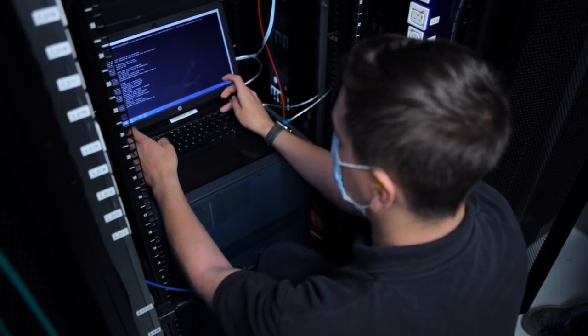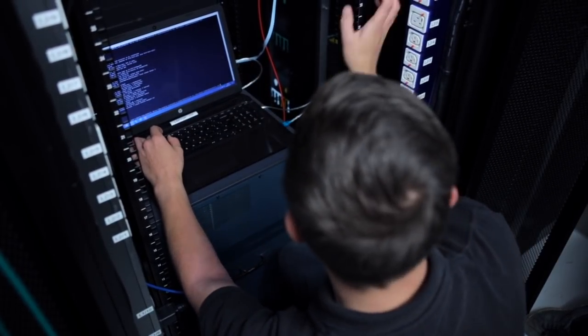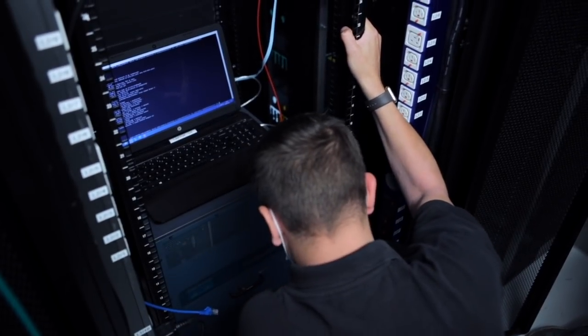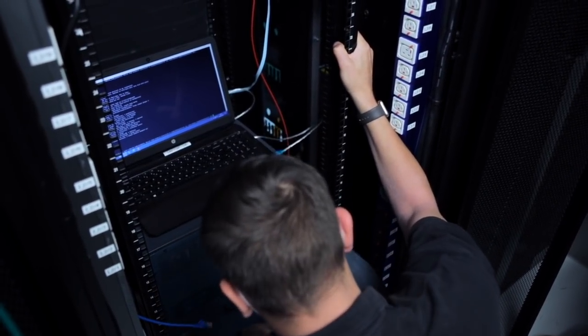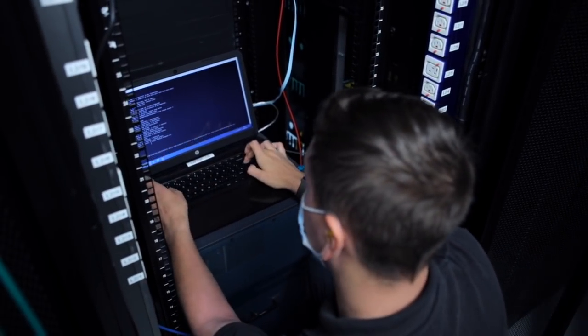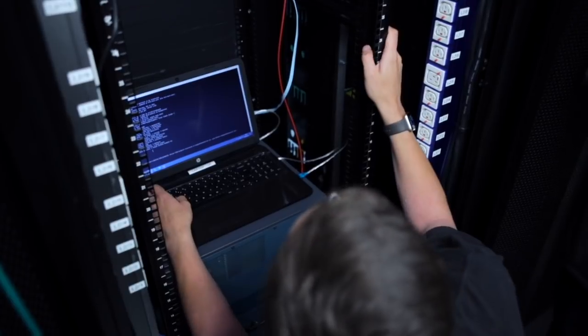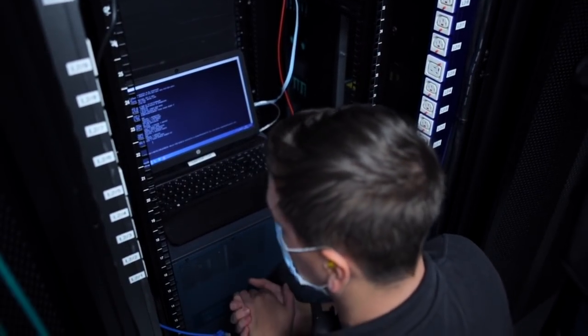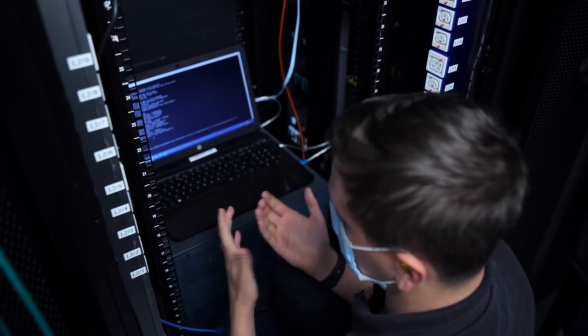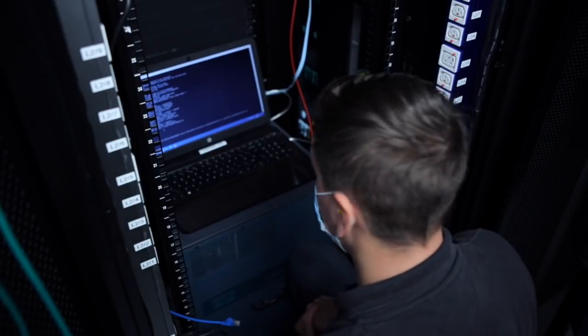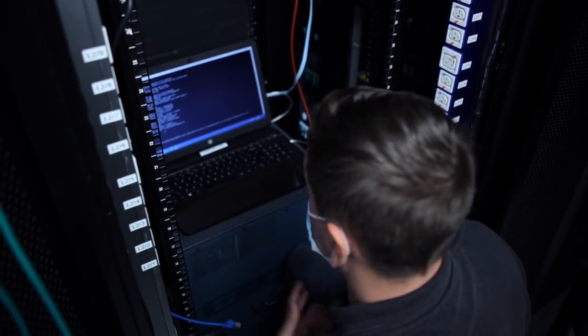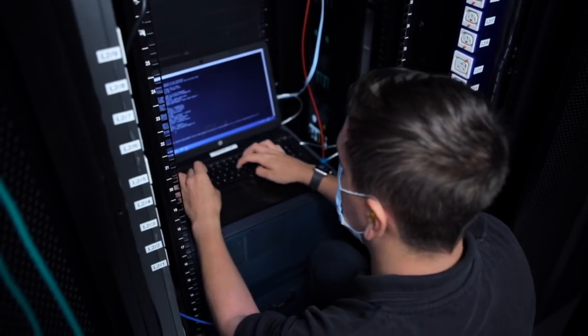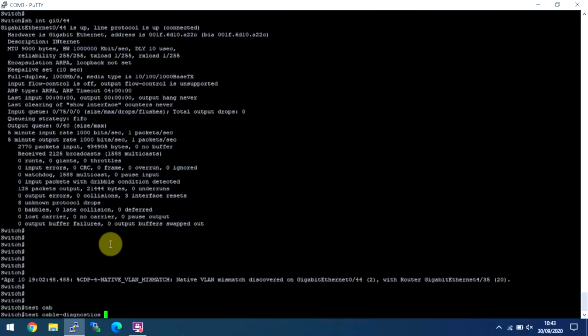What I'll show you now is the cable diagnostics. Now, James beside me has a pair of scissors and what we're actually going to do is we're going to cut one of the cables and then we're going to rerun the test so you can get an idea of what's actually happening. If I run the cable diagnostics before, it will do a TDR which will basically tell us the length and how it's wired, whether it's wired correctly, whether there's any short circuits or whether there's just wires or cores missing.